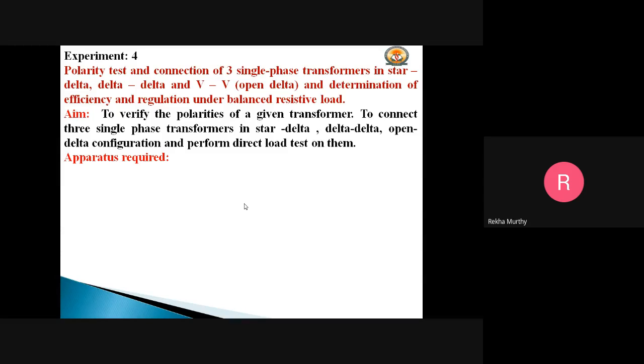If the EMFs induced in the primary and secondary are summed up instead, the voltmeter will indicate double the voltage, around 430 volts. In that case, it indicates that we have to interchange the S1 and S2 terminals.